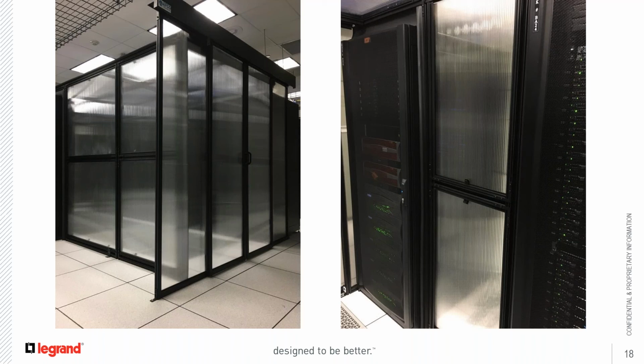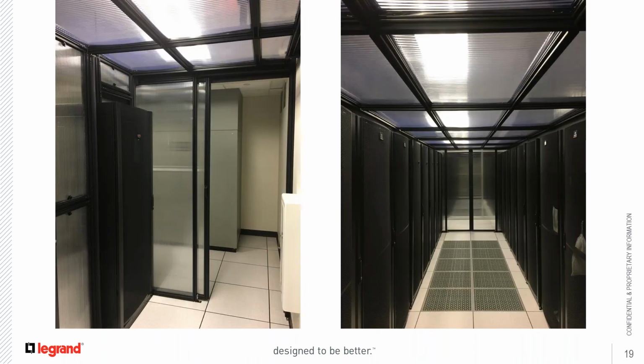The empty cabinet positions were filled in with vertical cap filler panels. The vertical location of the cold aisle containment roof was made uniform using filler panels above the cabinets to get a level playing field for the cold aisle to rest on.